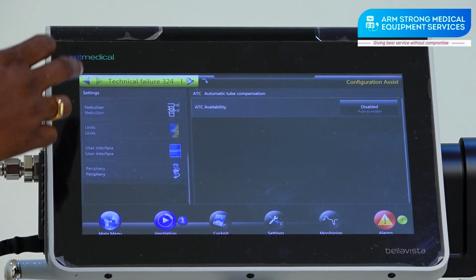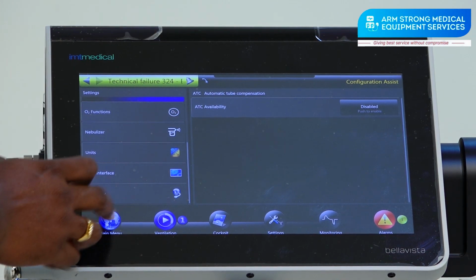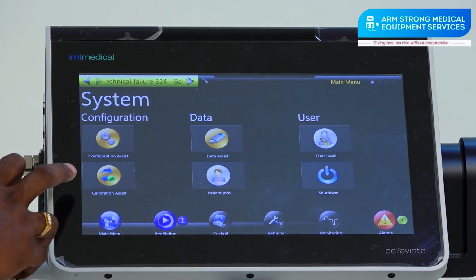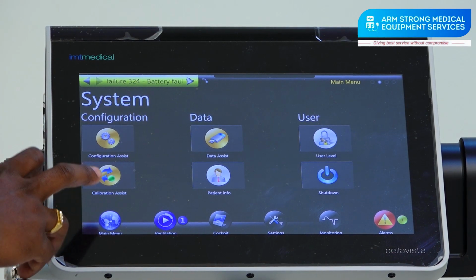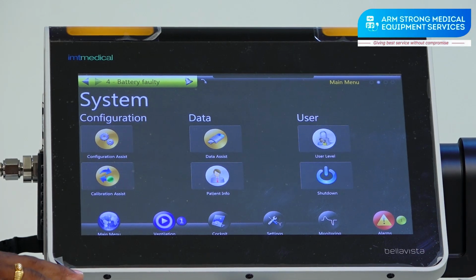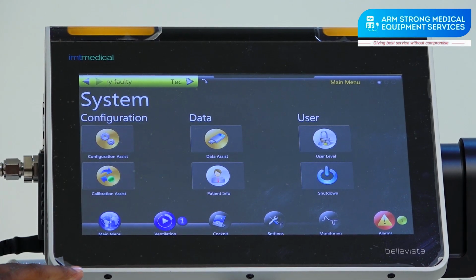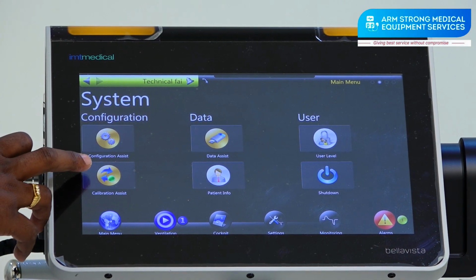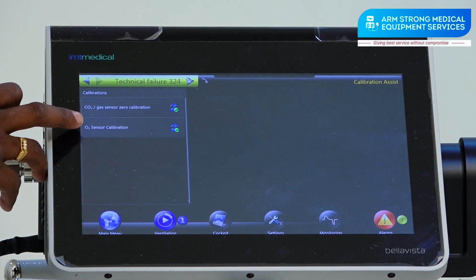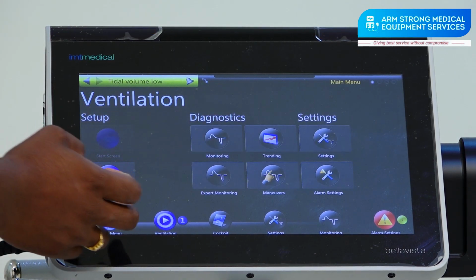And ventilator summary alarm, all these options are in configuration. And this is the calibration. The O2 cell is the galvanic O2 cell on this ventilator, so that is a consumable. If you want to do the calibration of that O2 sensor, you can go to this page.